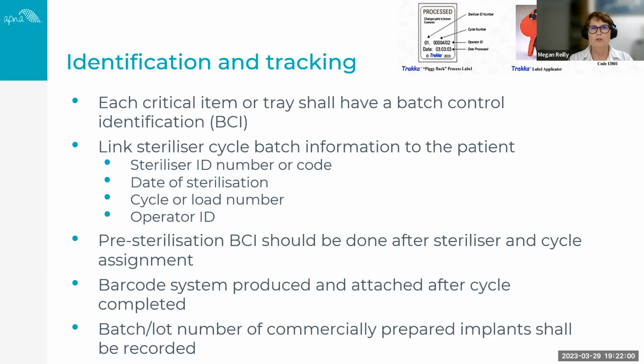For those of you who are using any sort of implant, usually this is purchased as a commercially prepared, sterile. You must record the batch lot or the batch or the lot number in the patient's record. So again, that can be tracked in the event that there was a requirement for that. So at minimum, the tracking or the traceability system shall be sufficient to enable the identification of a patient where a non-conforming item has been used in an event that a recall is necessary.